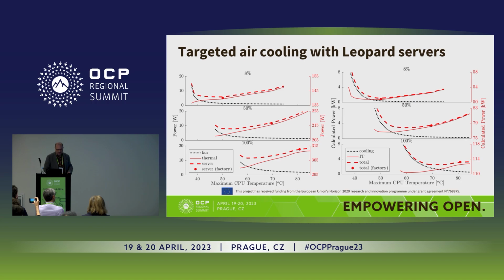But one of the things that we did find with these servers, and this is really interesting, is that the red dotted line, which is to be read on the right axis, is the power consumption of an individual server. At 8% workload is the top one, 50% the middle one, and 100% the bottom. The dotted red curve is the overall power consumption. The solid red curve is the thermal power, so discounting the fans in the servers, whereas the black dotted line is the fans in the servers. So what we were able to do, because we had control of the fans, was we could say, I want the CPU to operate at 60 degrees all the time.